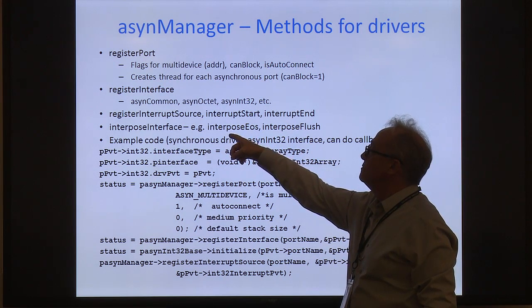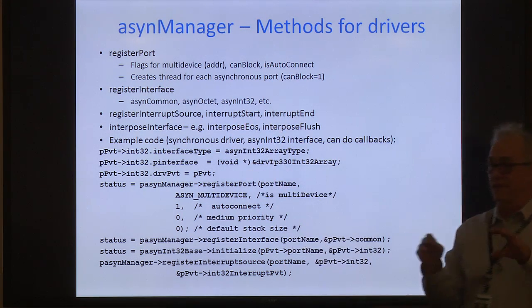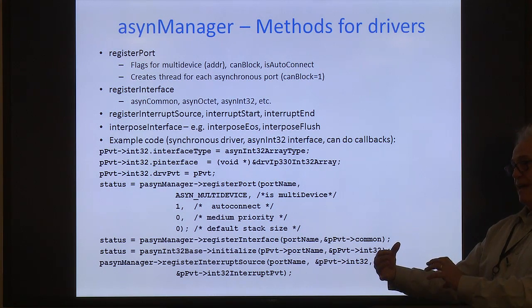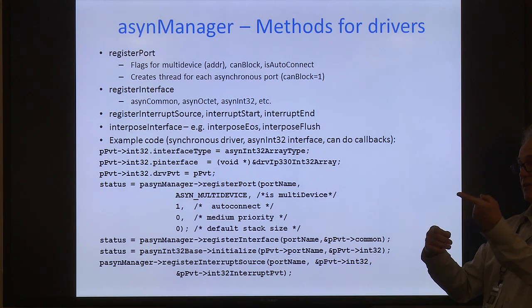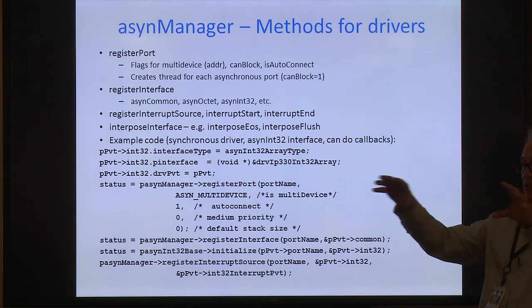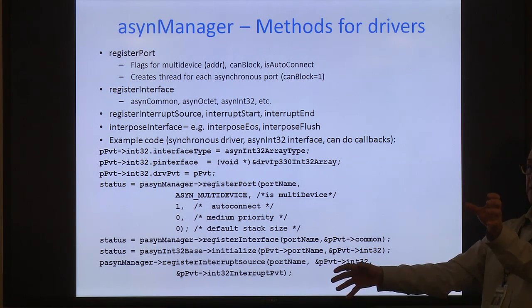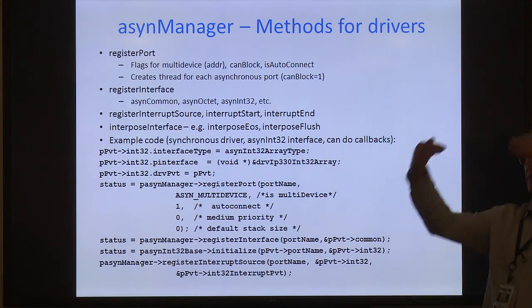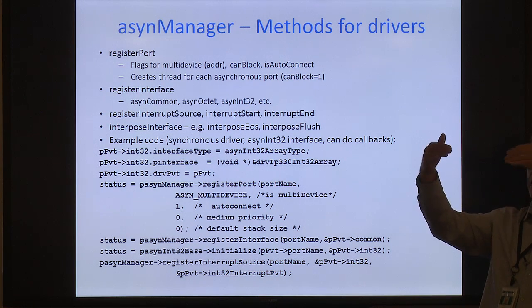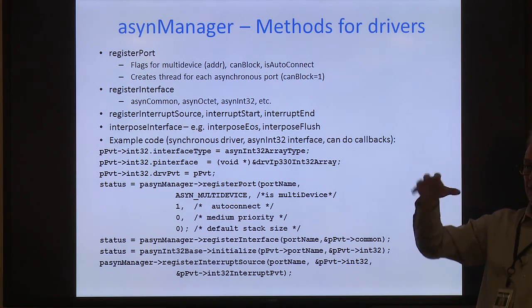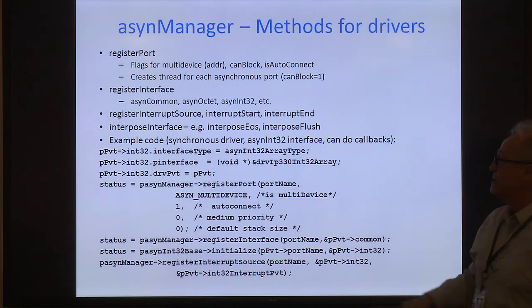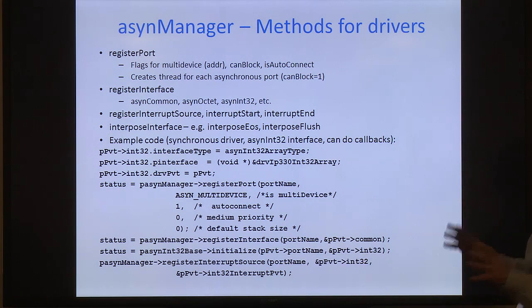And there are a few of these. For instance, with Modbus. Modbus is a communication protocol used with PLCs, and there's an underlying message. Then, depending on whether you're using serial ASCII, serial binary, or TCP, there's some header stuff that you have to put at the beginning of a message and a checksum at the end. So the driver is written to only package the message, and there's an interpose interface that says, okay, what's the other garbage I need to put at the beginning and at the end, and strip off on response. So interpose interfaces are useful, but they're fairly rare.